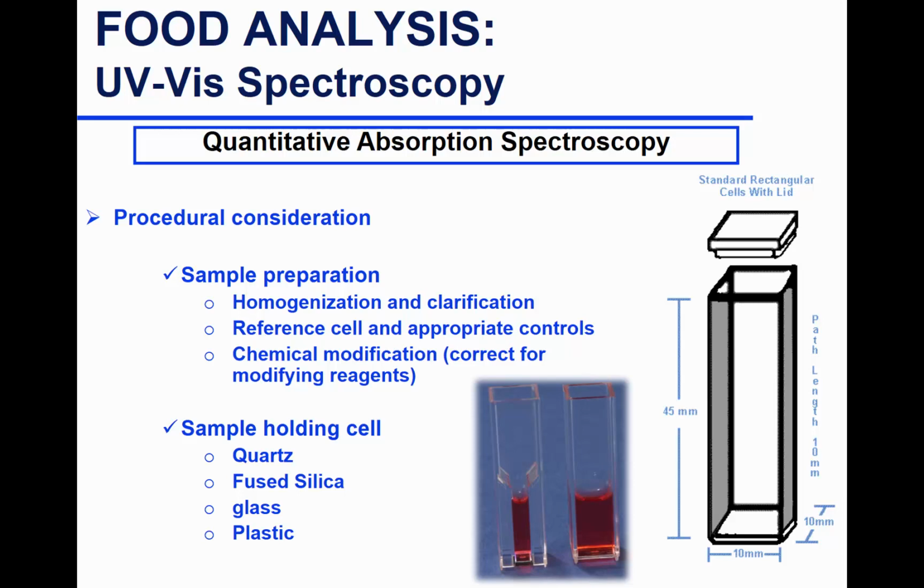And there are different types of cuvettes that you can get. You can see the regular cuvette size, which can take, what, 1.5 milliliters. But sometimes you don't have that much sample. Sometimes you are limited in your reaction. So you can purchase actually a cuvette that allows you to put less and still maintain the same height. The height is important because you want the beam of light to pass through here. If this is half empty, then the beam of light will pass through air. So the height is important for your sample and the path of light, where the light is hitting your sample.